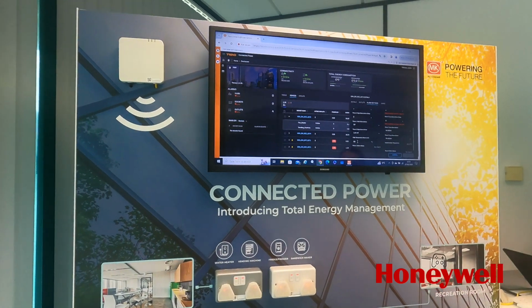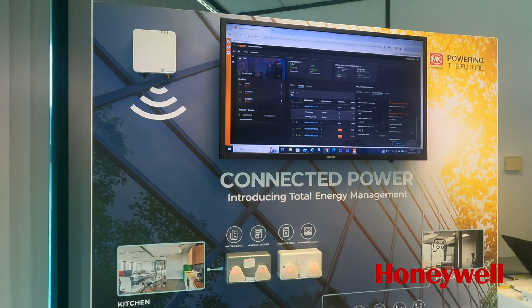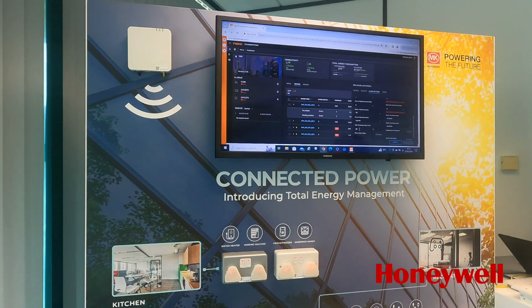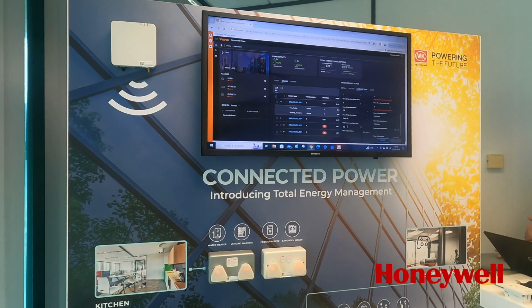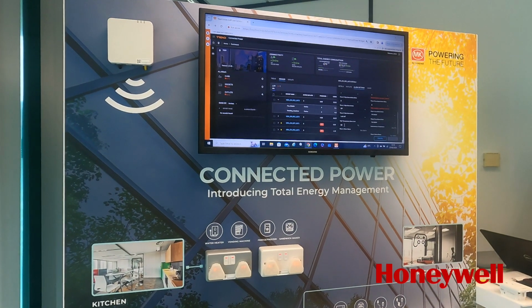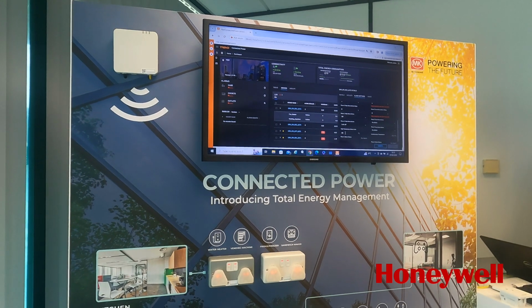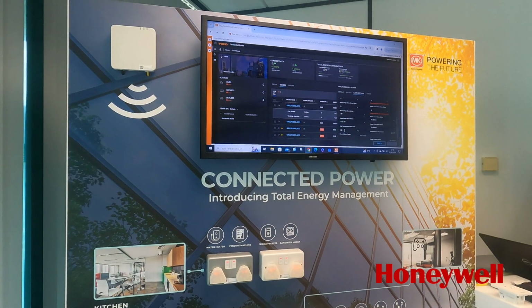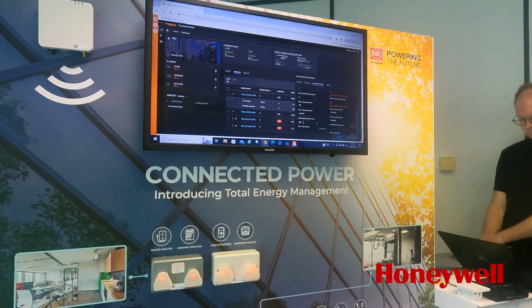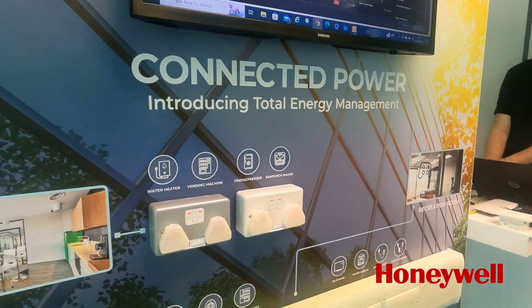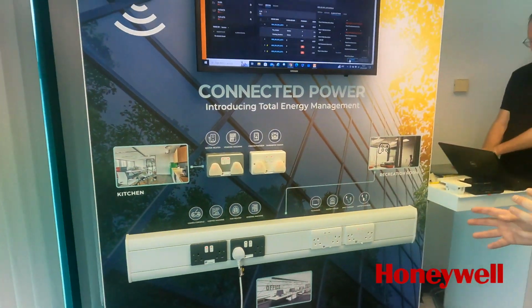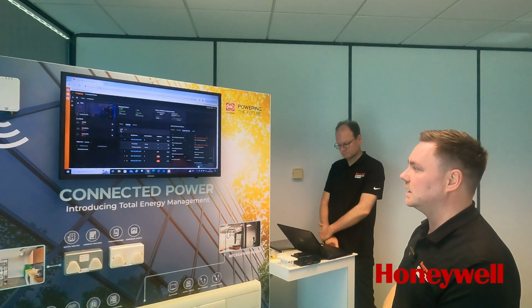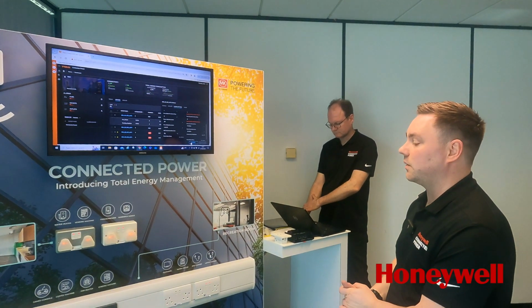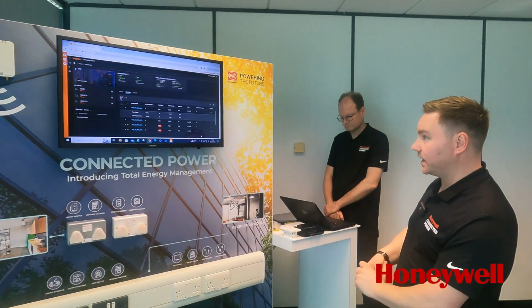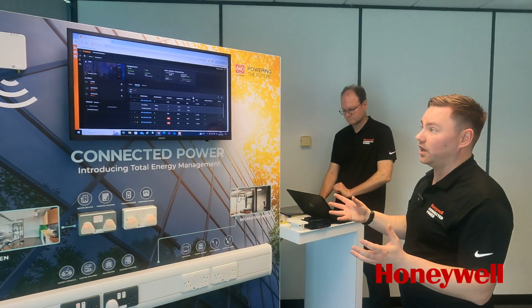This gives us an early indication that something might be going wrong with our socket, whether that is termination of cables becoming loose, or the appliance developing a fault and drawing more current than it should, which builds up resistance and would also build up heat. So it could be various things, but this gives us an early indication as to what's going on. So that is our dashboard as a whole.